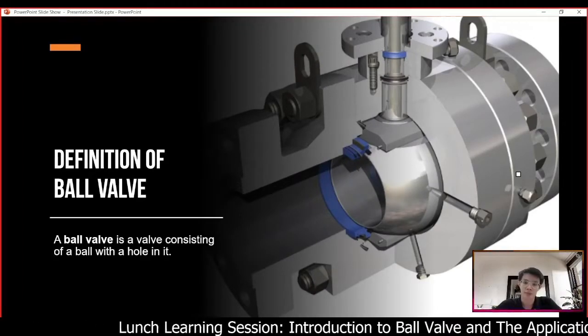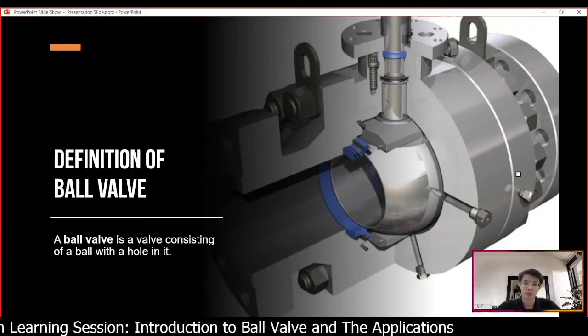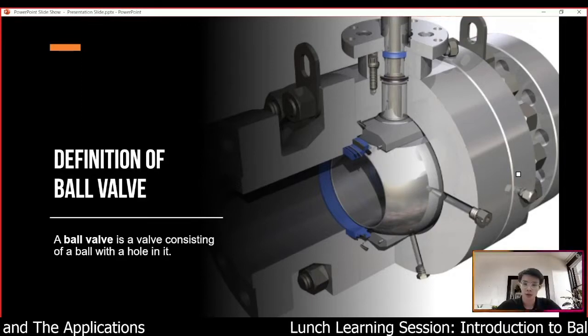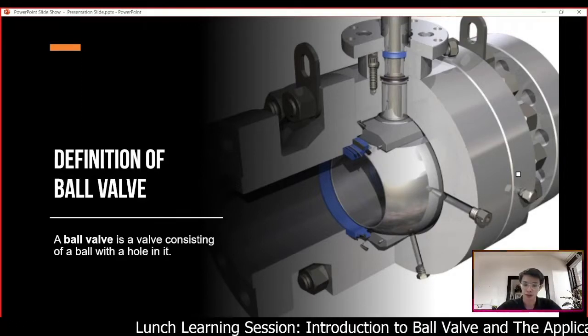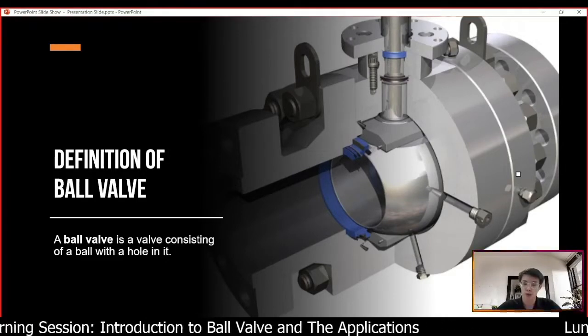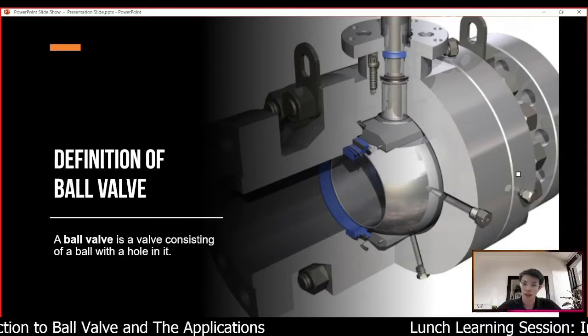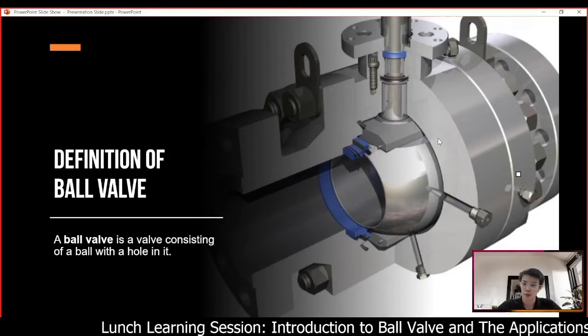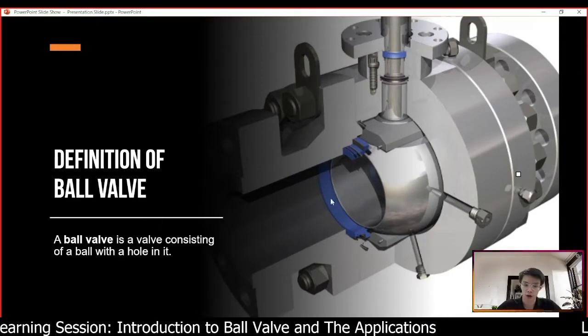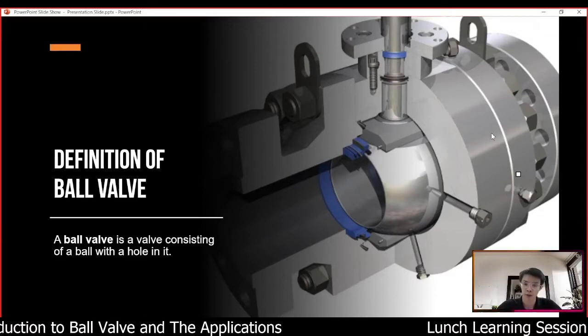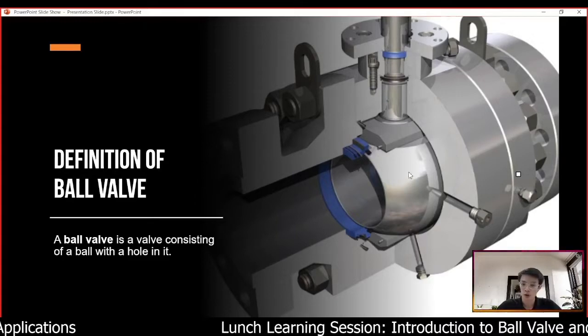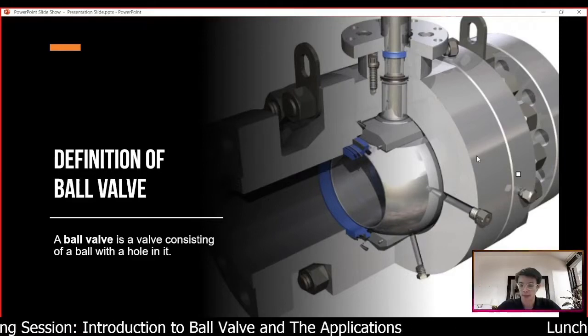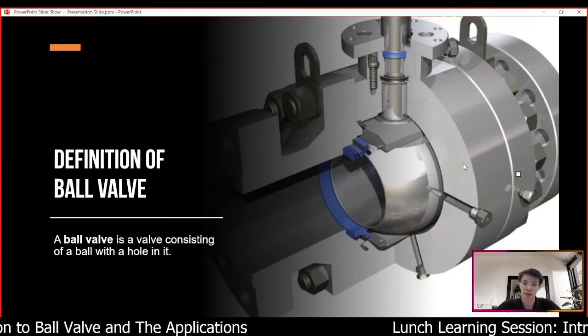First of all, what is a ball valve? The definition of a ball valve is a valve which consists of a ball with a hole in it. A ball valve is a quarter-turn rotational motion valve that uses a ball-shaped disc to stop or start the flow. To allow flow to pass through, the ball rotates to a point where it is in line with the hole through the pipe inlet and outlet. To close the flow, the ball is rotated so that the hole is perpendicular to the flow and blocks the flow from passing through to the downstream.